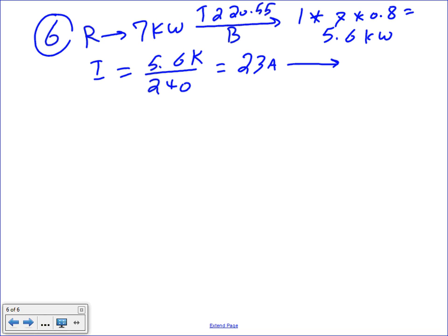Now take this one to 310.15(B)(16), under the 60 degree column. What's the conductor? 30 amps, number 10. So 3 conductors, number 10, and the overcurrent protection device. What's the next overcurrent protection device? The next overcurrent protection device, I can use 25 here.